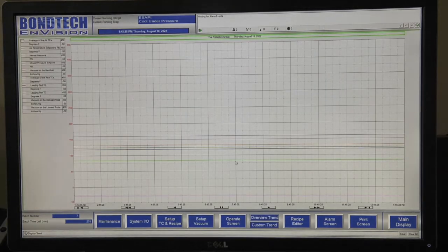The overview trend will show you the actual trend of the process of what is happening within the system. So we have what the thermocouples are doing, reaching up to the particular temperature that is set, as well as the vacuum, and the lead, lag, and average of the thermocouples as well. A lot of what the end user essentially wants is that trend screen, to actually see that it is meeting the parameters that were set originally. They can use it for their editing purposes.